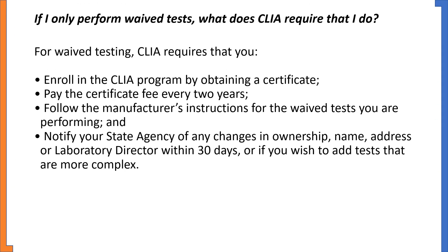If I only perform waived tests, what does CLIA require that I do? For waived testing, CLIA requires that you enroll in the CLIA program by obtaining a certificate and pay the certificate fee every two years. You must also follow the manufacturer's instructions for the waived test you are performing.